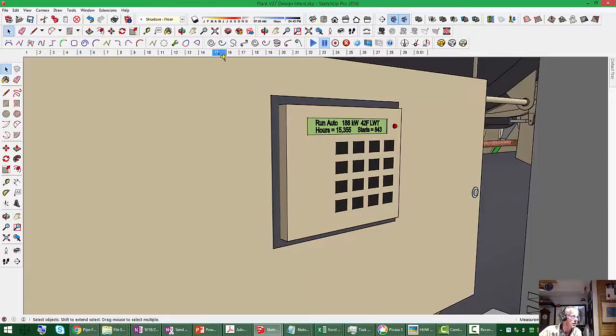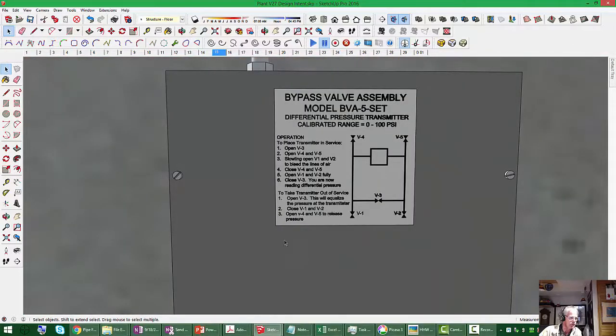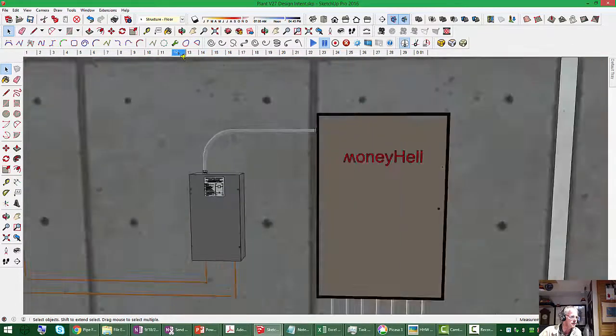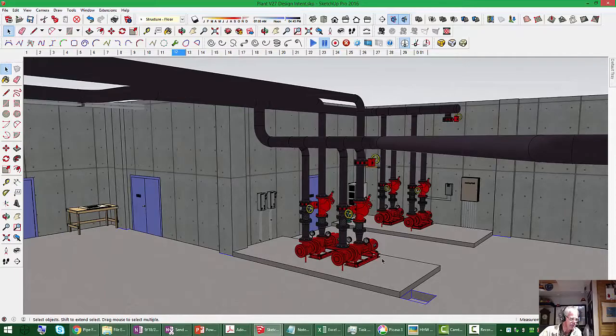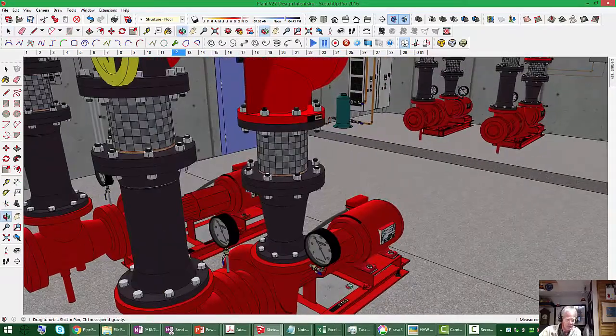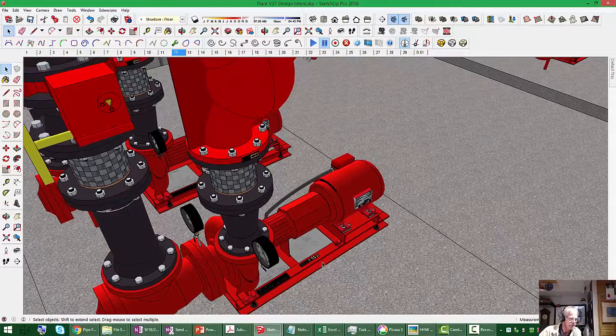And so if we go back and look at the evaporator pump, 1100 GPM at 2 GPM a ton would basically mean that's about a 550 ton machine. Okay, so we have a plant that's probably in the range of 1100, 1200 tons of capacity that right now might be running with one machine 50% loaded or not.